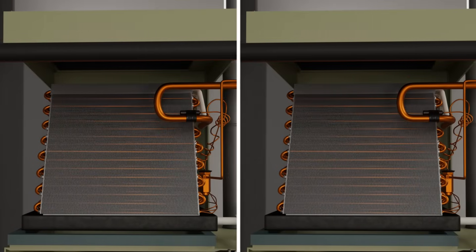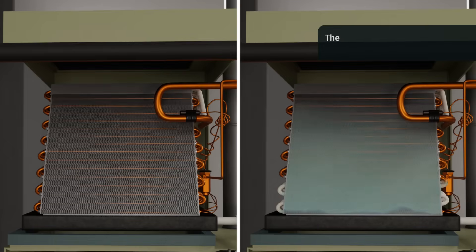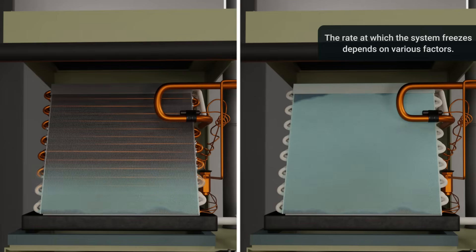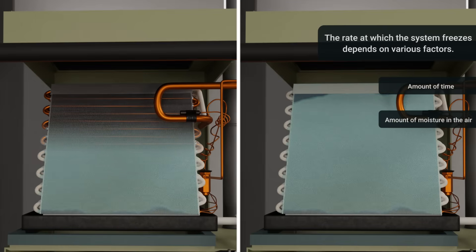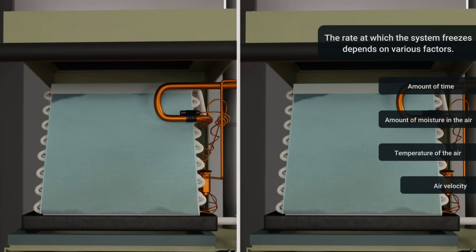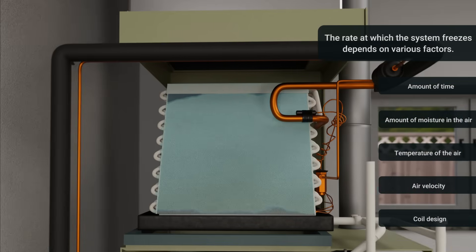When freezing does occur, the rate at which the system freezes depends on various factors, including the amount of time, the amount of moisture in the air, the temperature of the air passing over the coil, air velocity, and coil design.